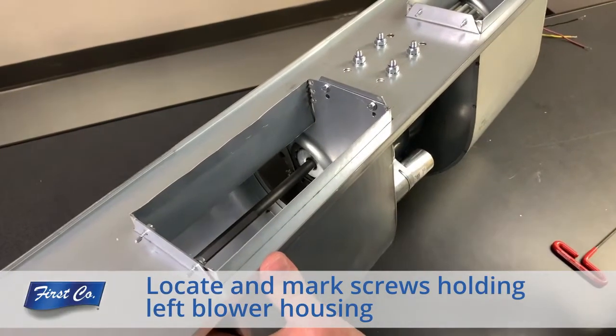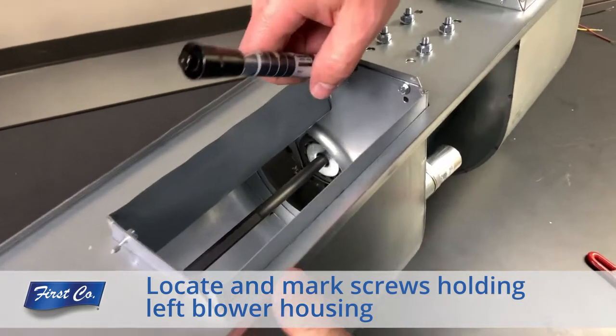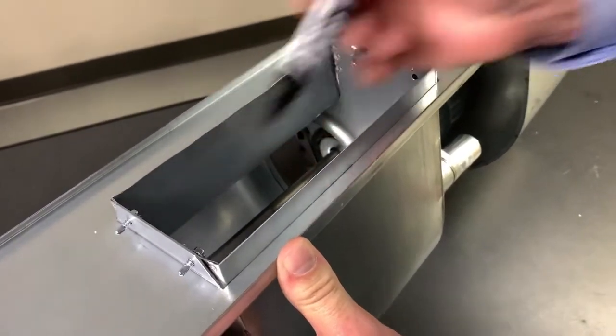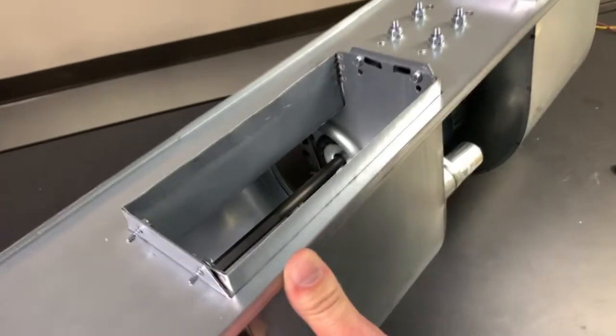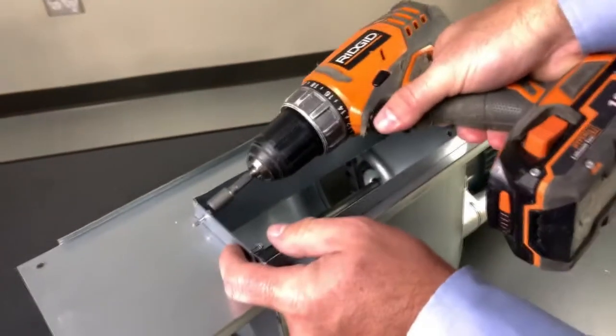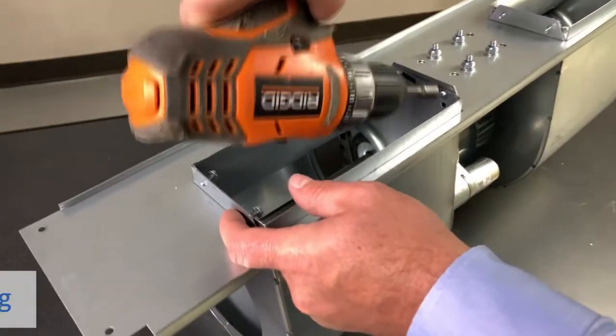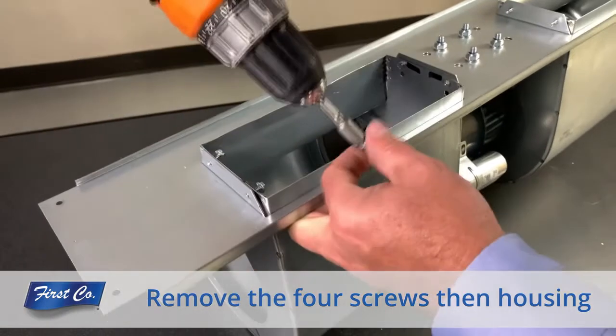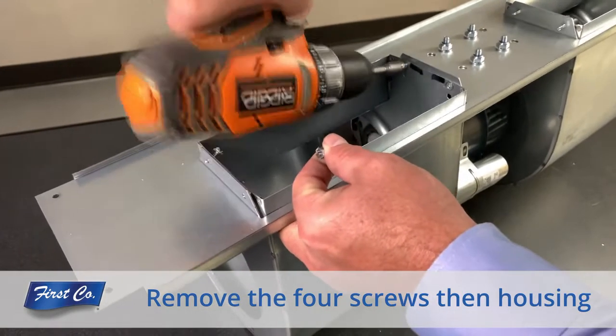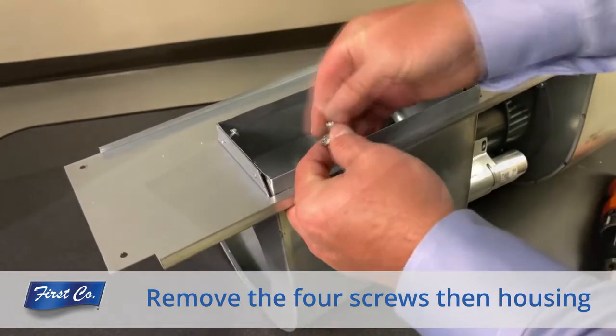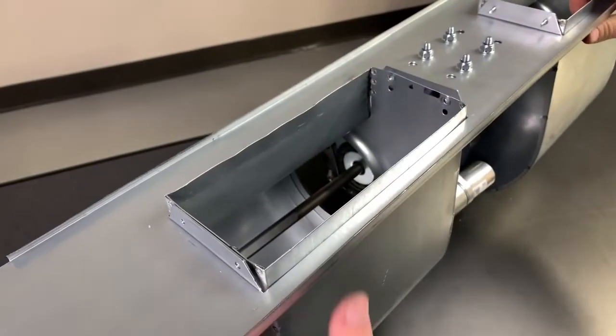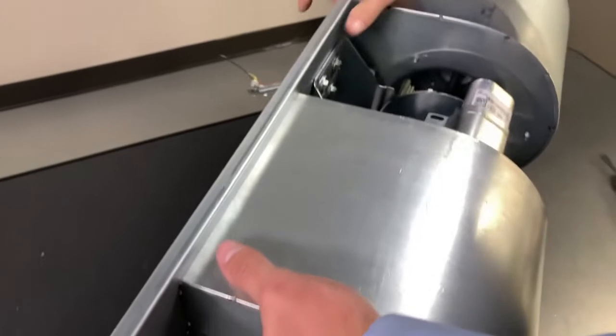Locate the four screws holding the left blower housing and mark these holes. You only need to remove the left blower housing to remove the motor. Remove the four screws and then remove the housing. This allows access for the motor to be removed.